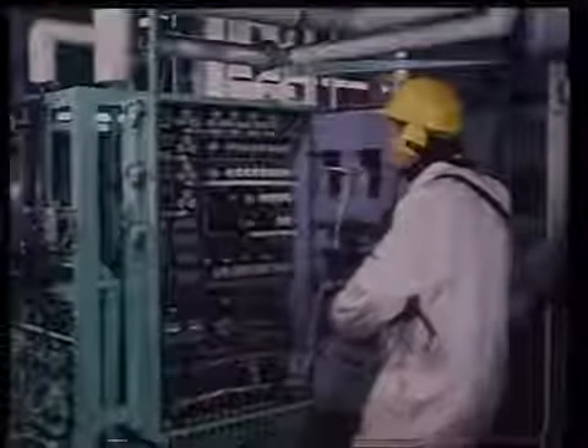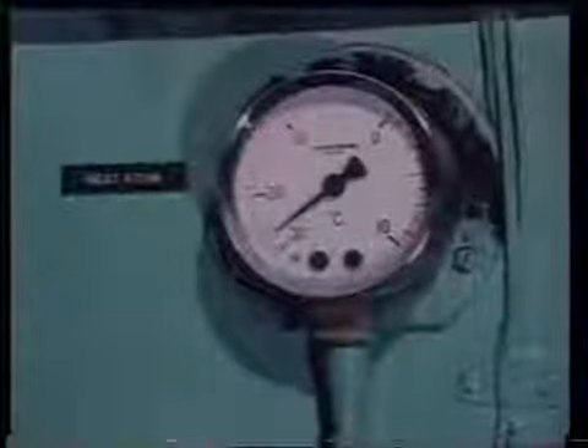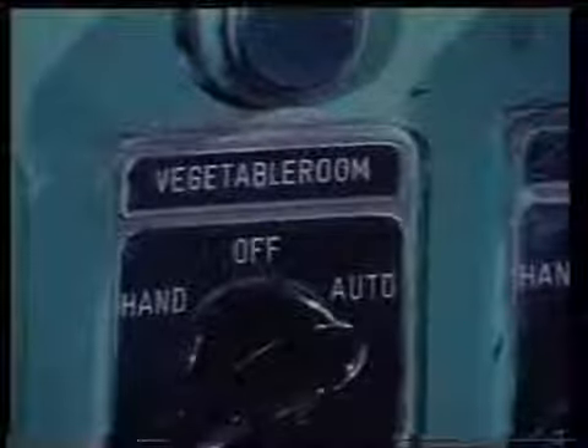Now let's have a look at some ancillary circuitry, such as the refrigerating plant, alarms and emergency stop buttons. First, the refrigerating plant. The refrigerating plant for the meat room, the flour room and the vegetable room is controlled via a common panel. This panel houses the relevant direct online starters which connect the appropriate motors to the supply when activated by a thermostat. In case of malfunction, check the thermostat and the solenoid valves for correct function. These sometimes get stuck in a closed or open position.